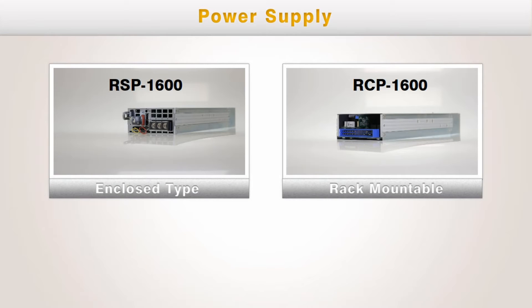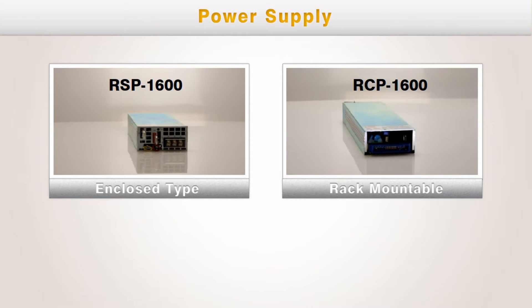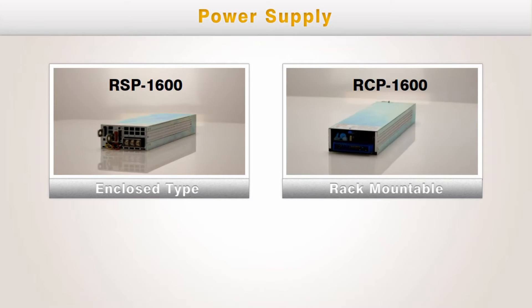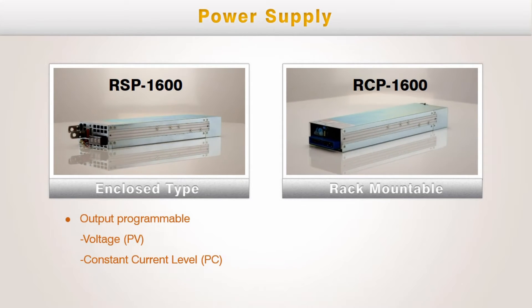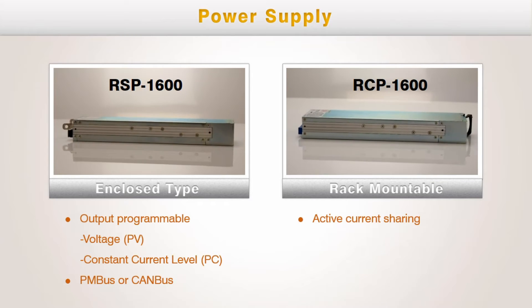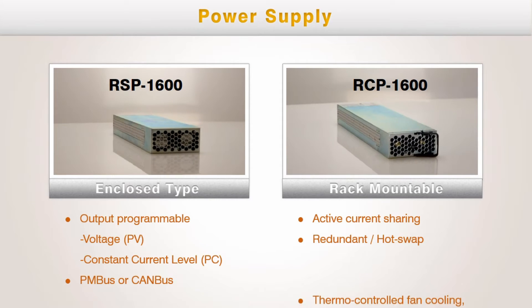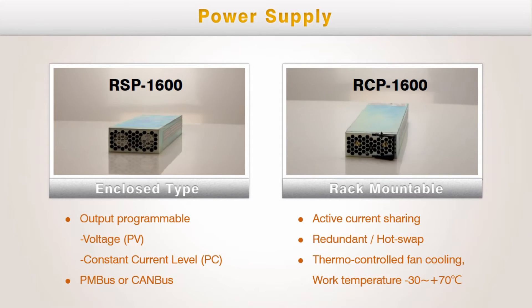Based on one primary spec, the two input/output connection styles, RSP and RCP, are the power supply solutions. Various functions are equipped on RSP/RCP-1600, such as output programmable function, communication interface, active current sharing, and redundant or hot swap capability. A cooling fan is built into each series with the fan speed changing according to temperature.